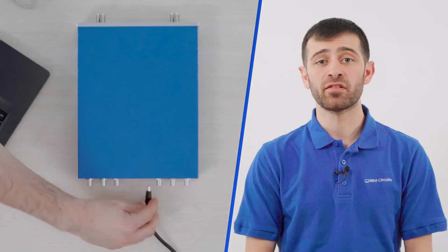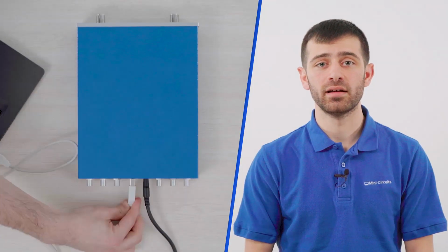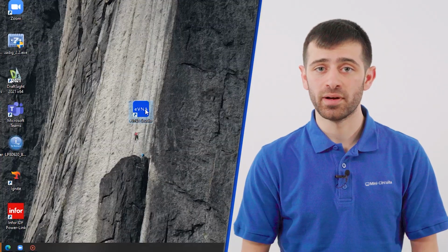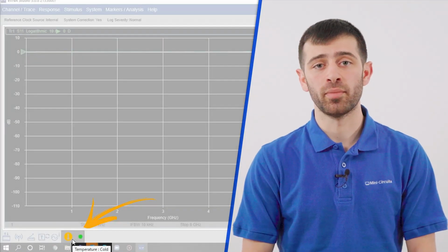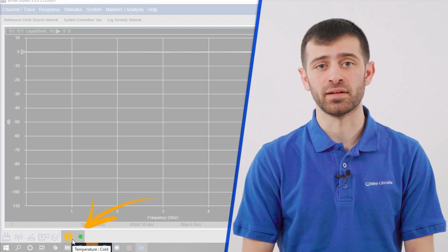Before we get started, feel free to take a look at the other videos in the series covering the initial setup and calibration process. We can start by powering on our eVNA, connecting it to our PC, and opening the eVNA Studio software. As always, let the device warm up until the temperature indicator turns green.